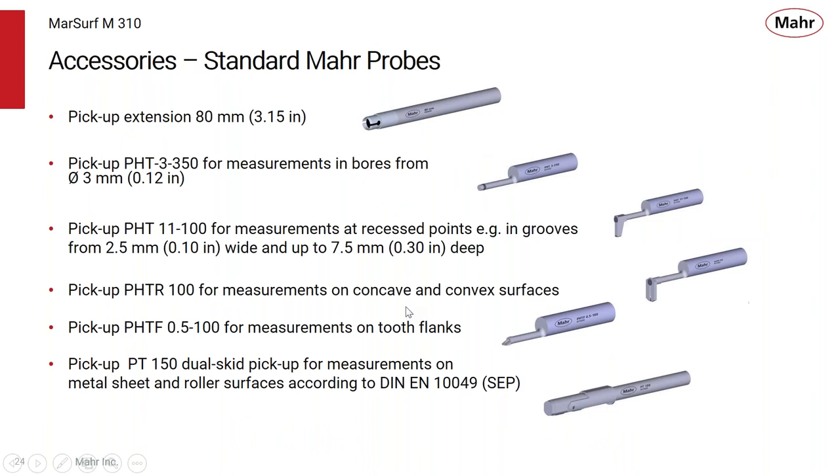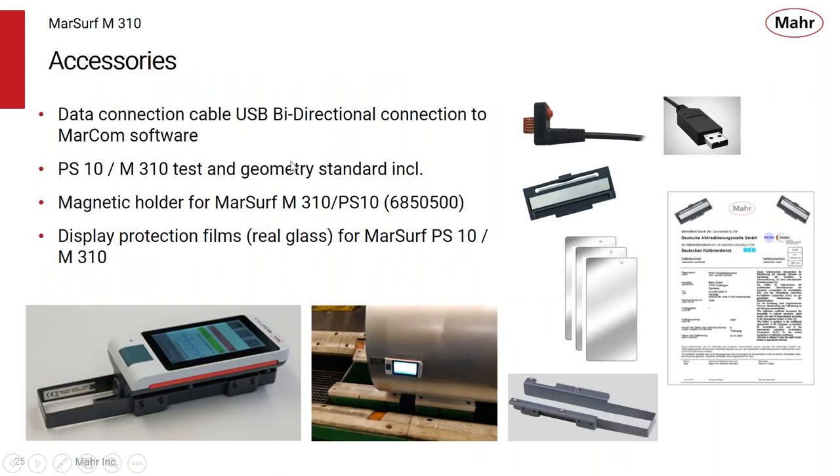All the accessories available for other Mahr roughness products like the PS10 are compatible with the M310. Mahr makes probes for small bores, deep grooves, measuring gear tooth flanks, and extensions to allow the probe to reach further into a small bore — all standard accessories are compatible with the M310. The data connection cable is bi-directional so you can not only receive information but also send data to the M310 to program it, tell it when to start, and set tolerances.